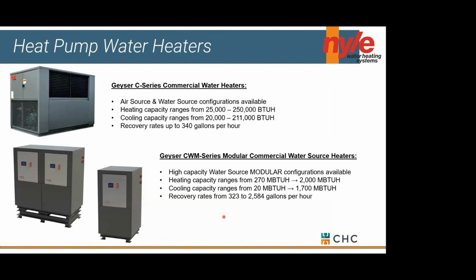Let's look at another one, if you're still with me. And that's heat pump water heaters. Definitely picking up a lot of traction. How are these guys working? Well, they're using something we call the refrigeration cycle to simply transfer heat into domestic water, and then also take some warm air that might be in a server room or a parking garage or outside source, to take our refrigerant and turn it back into vapor and continue our refrigerant cycle.